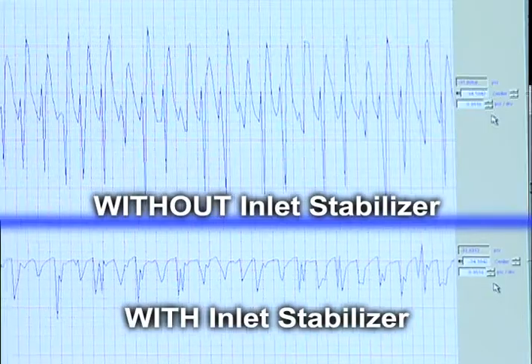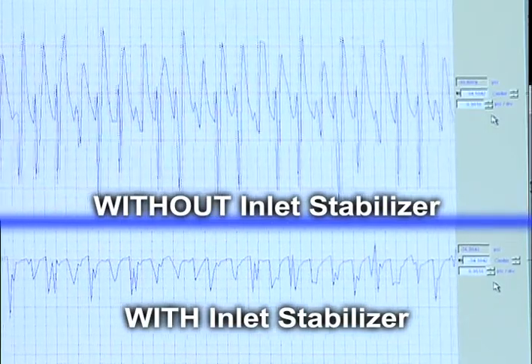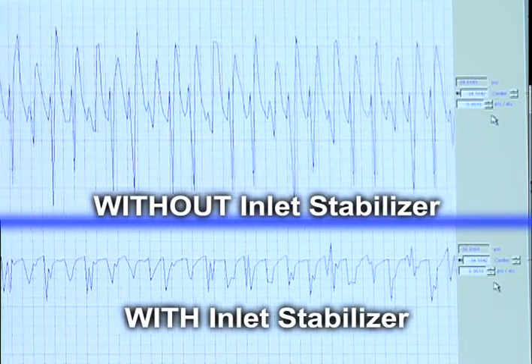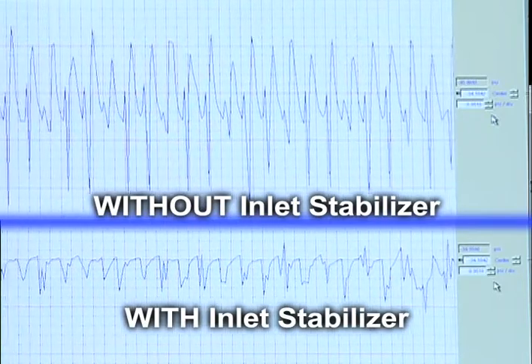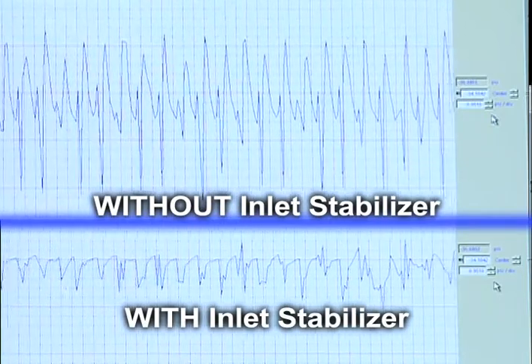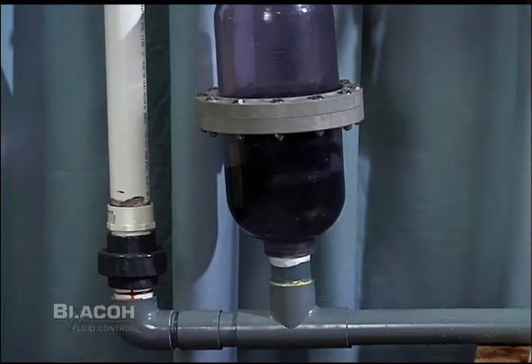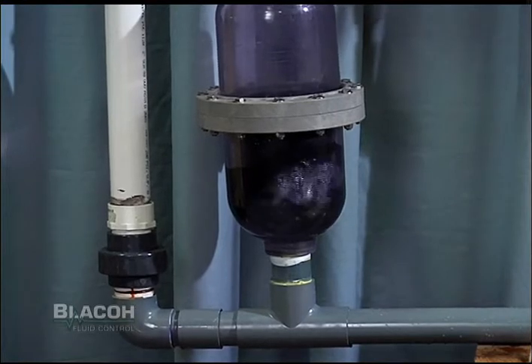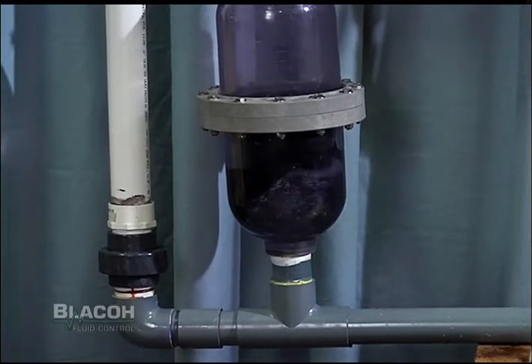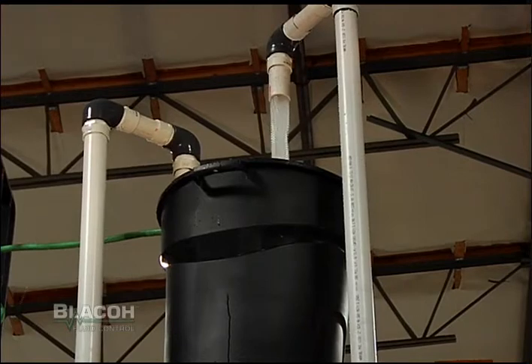Now that the inlet stabilizer has been adjusted by lowering the pressure charge within it, if you notice on the transducer, the pressure spike has been absorbed by the inlet stabilizer and the inlet pressure has now been reduced significantly. That amount of pressure spike is well within the limit of the air diaphragm pump and no damage will occur to its diaphragms. The valve balls will seat more positively and there is less chance of cavitation because we are accumulating liquid right at the pump's inlet.